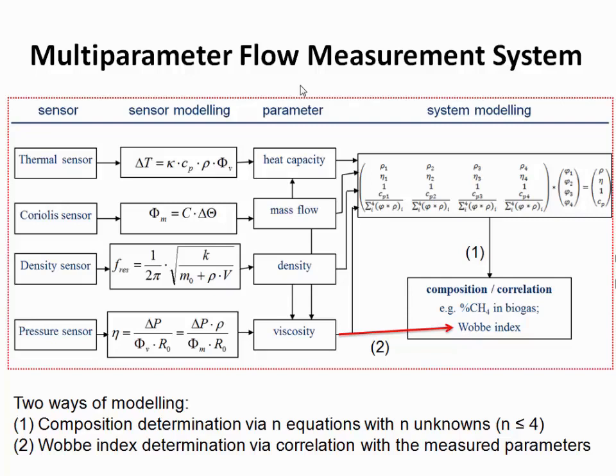So when we compare these two signals, we also get the heat capacity of the gas mixture. Of course, the density sensor provides us with the density of the gas mixture, and then the combination of density, mass flow, and the output signal of the pressure sensor provides us with the viscosity of the mixture. So that's the first stage. Now we have derived all the parameters of the mixture, and now we can go into the system model, and there we can derive the composition or the Wobbe index.